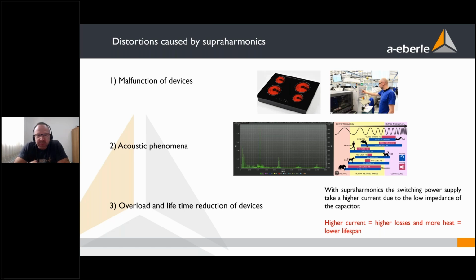So what are the problems with supraharmonics or high frequency in the network? One of the reasons is maybe a malfunction of other devices. Other devices work with small signals, and if a high frequency goes into such a device, it can stop or start, or you have some wrong operation. The next phenomenon could be an acoustic problem, that you can hear maybe 4 or 8 kilohertz from other devices.